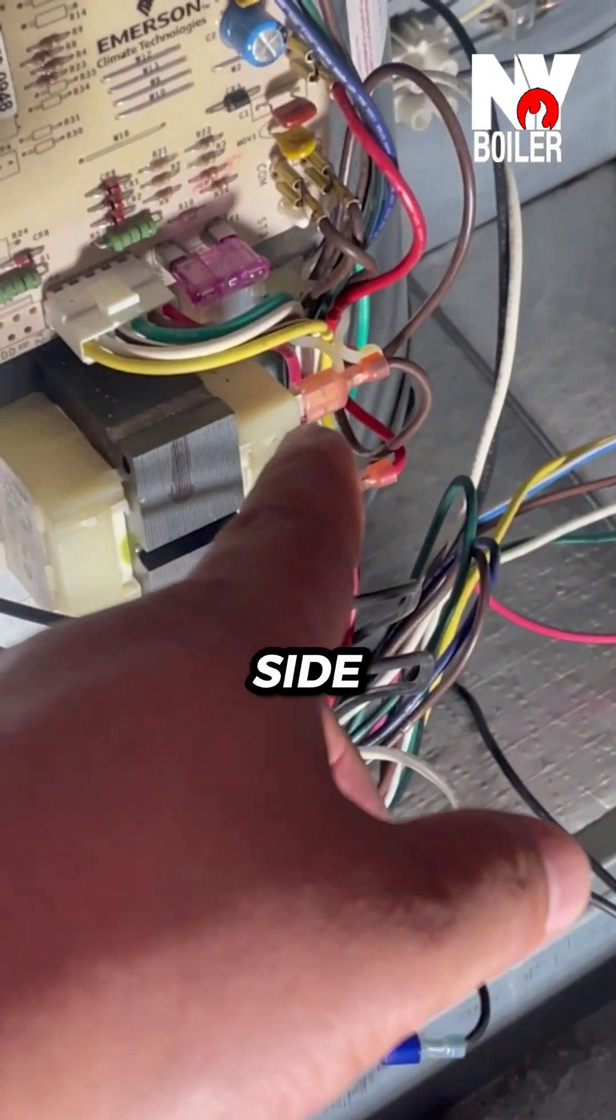All right guys, I'm going to take you through the process of troubleshooting this ECM motor. So I got 24 volts because I confirmed we have 24 volts coming from this side, so you need to put your volt meter from here to here, get 24 volts.